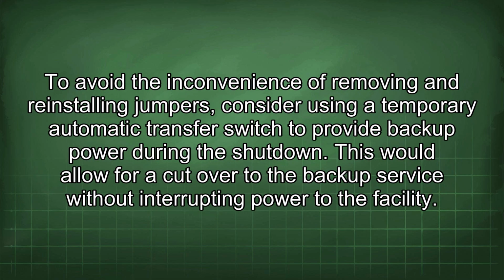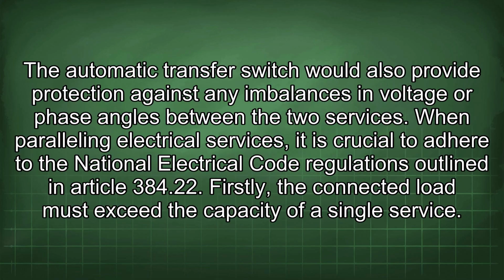To avoid the inconvenience of removing and reinstalling jumpers, consider using a temporary automatic transfer switch to provide backup power during the shutdown. This would allow for a cutover to the backup service without interrupting power to the facility. The automatic transfer switch would also provide protection against any imbalances in voltage or phase angles between the two services.